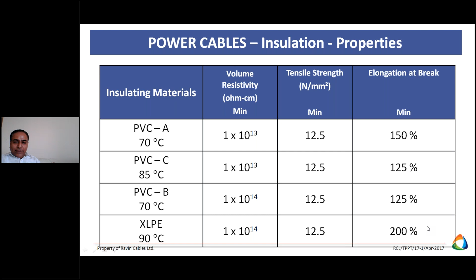Full form of PVC is polyvinyl chloride. XLPE is cross-linked polyethylene. The basic difference is: PVC is a reprocessed material, or thermoplastic material in technical terms, while XLPE is a thermoset material. Thermoset materials are processed once and cannot be recycled or reversed. So XLPE is thermoset, PVC is thermoplastic. That's the first basic difference. Then, operating temperature of XLPE is 90 degrees and PVC is 70 degrees.